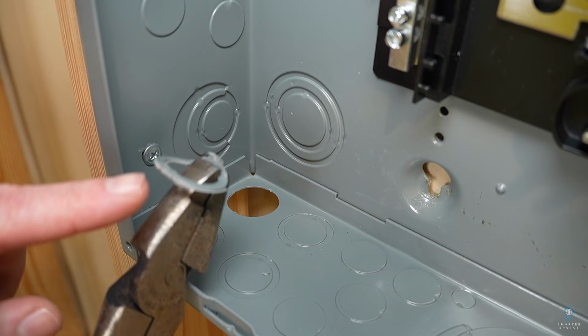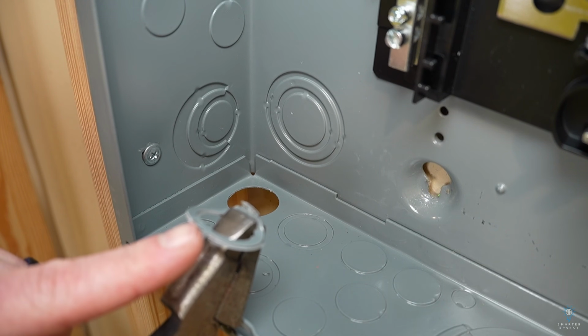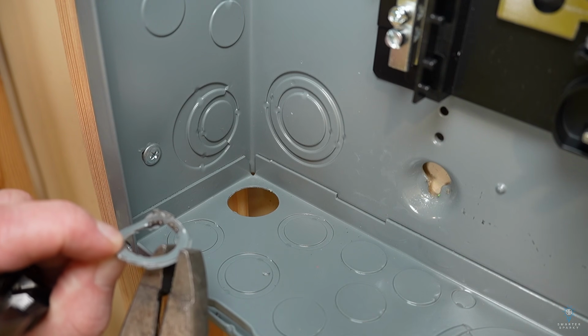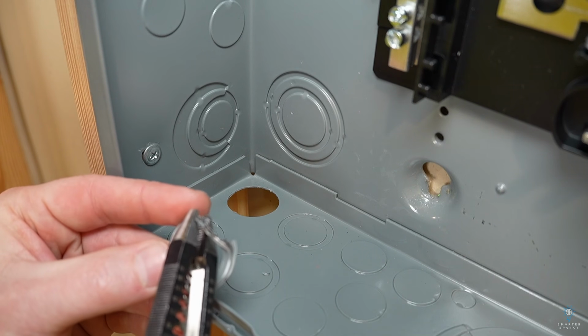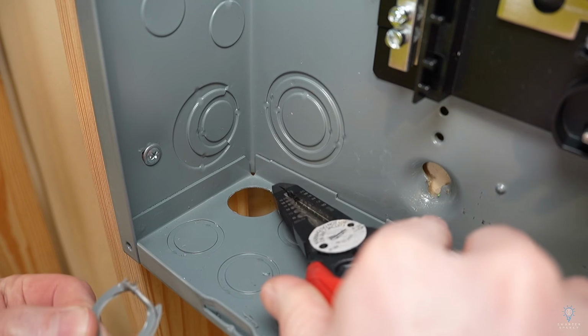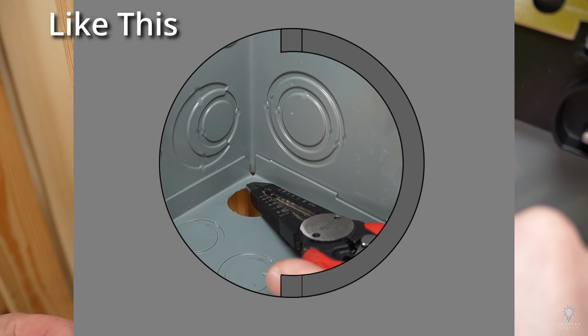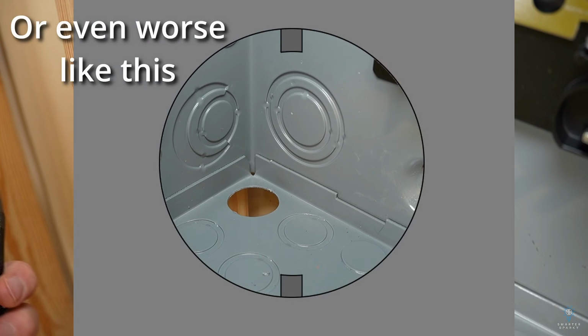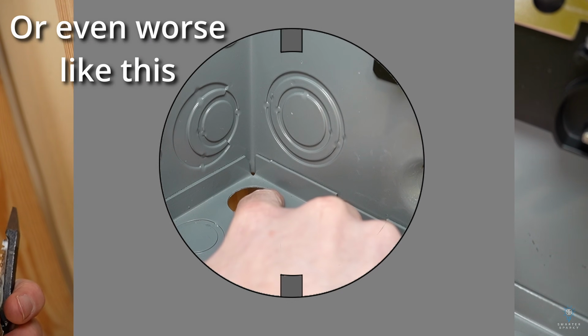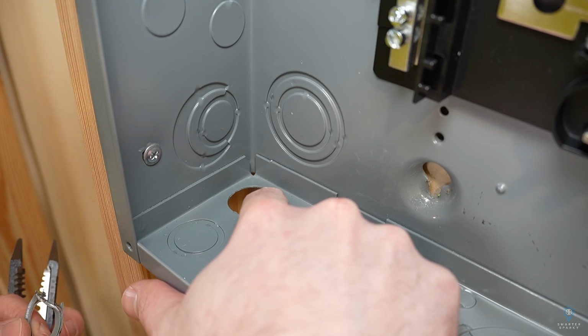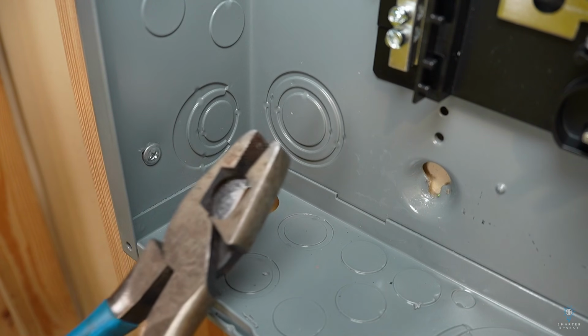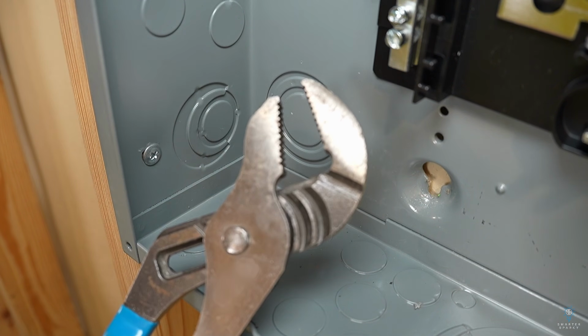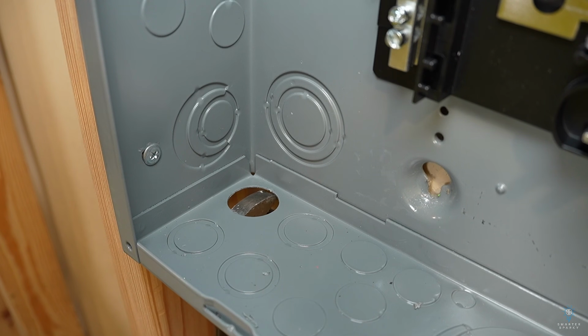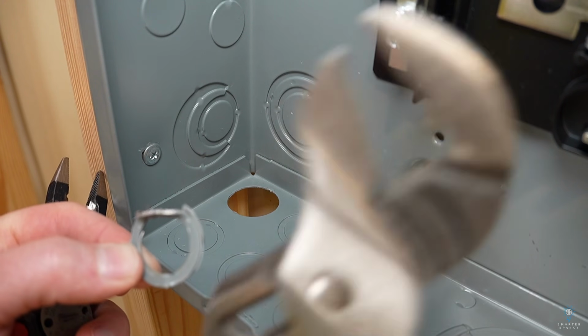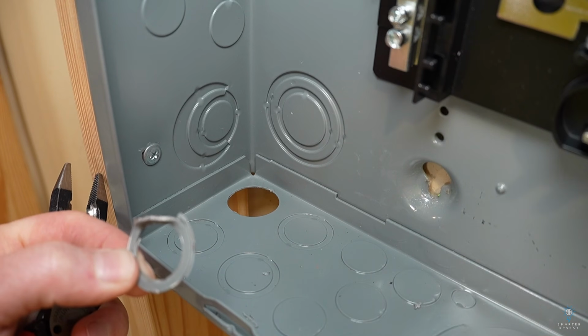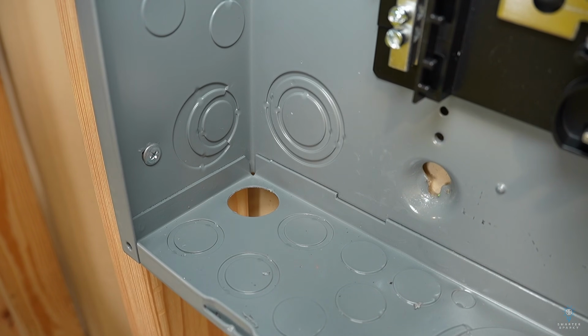The reason I'm doing it this way is I have found in the past that some of these panels are not punched very well, and if you just grab a corner like over here, or you grab it with just a needle nose, it'll actually break off right before that connection point. So then basically it'll break off just under half of that knockout ring, and then it kind of puts you in a situation where you've got to grab those connection points a little bit more firm and break them off separately. So I've just found it better right away to grab the whole joint with either a lineman's pliers or something like a channel locks or a Knipex and get in there and grab that entire joint and break the joint itself rather than relying on the actual metal of the knockout to actually break the joint. That's probably one of those things that make no sense unless you've been there and had to deal with that.